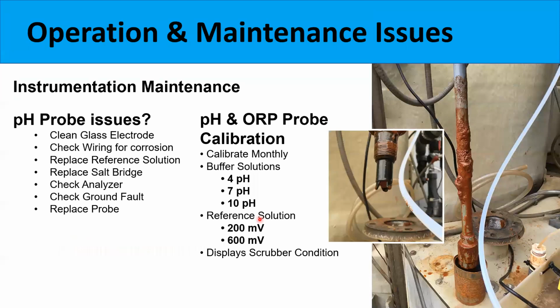All wet scrubbers have some level of instrumentation, and some of the most common instruments found on scrubbers are the pH probes and ORP probes. pH probes are obviously used for neutralization. In this case, we have a very contaminated sump and an iron deposit that's been built up on this pH probe shaft here, and then the inset picture has some buildup on the actual glass electrode of the probe.